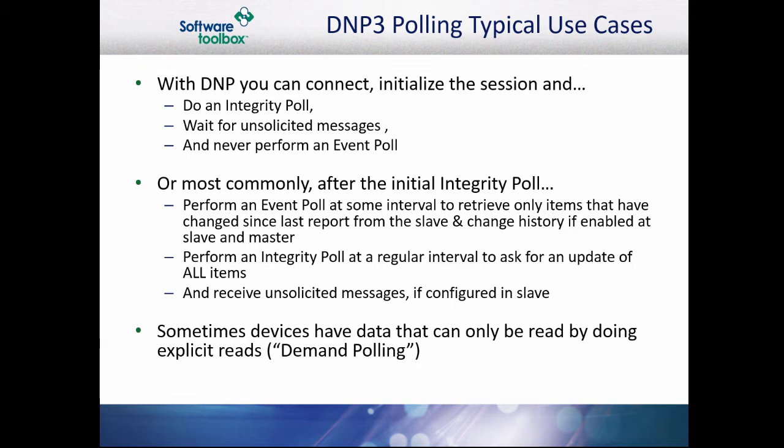More commonly, we see the event poll and unsolicited messaging mixed. After the initial integrity poll, you will perform event polls at regular intervals, integrity polls at infrequent intervals, and listen for unsolicited messages if the slave is configured for such. Sometimes devices have some data points that can only be read explicitly from the device — this is the demand polling option. The only other use case we have encountered for demand polling is regulatory reporting requirements that require a point or points to be reported at specific intervals regardless of value change.